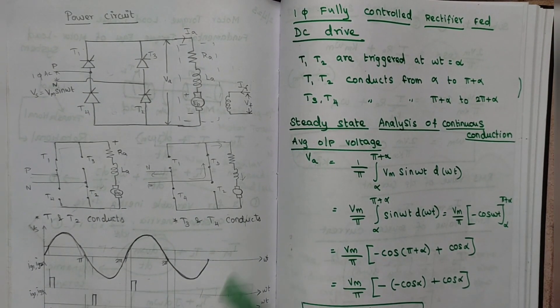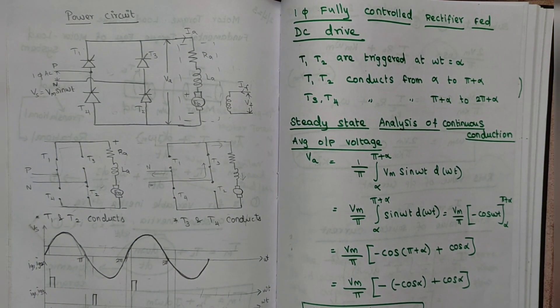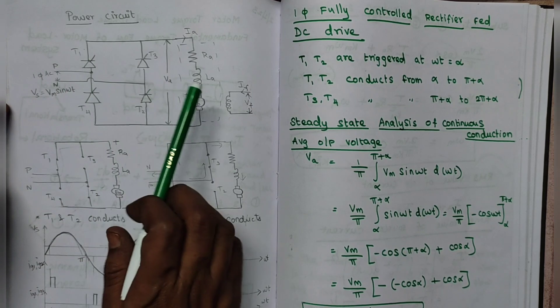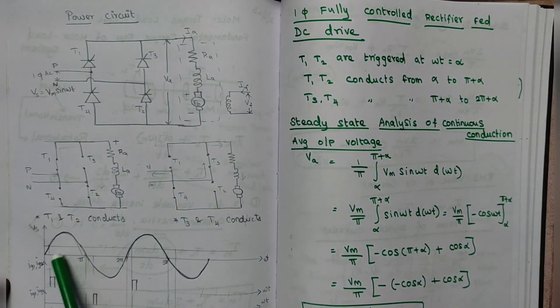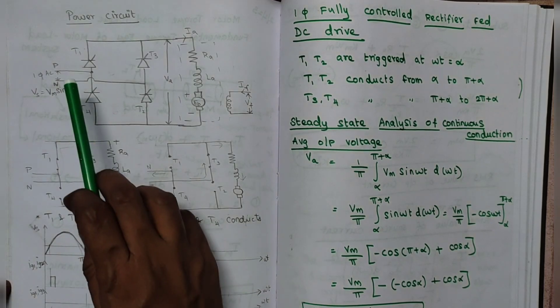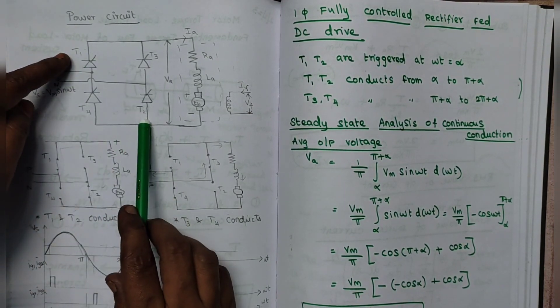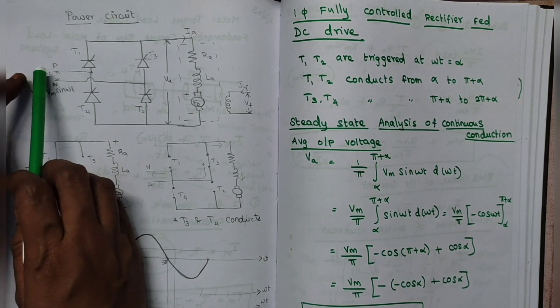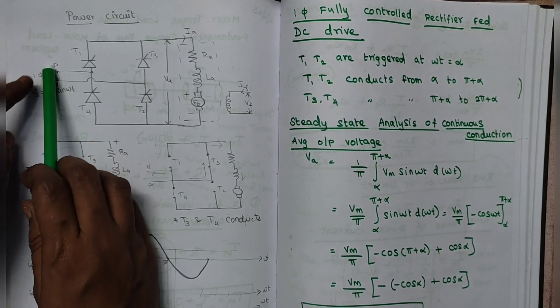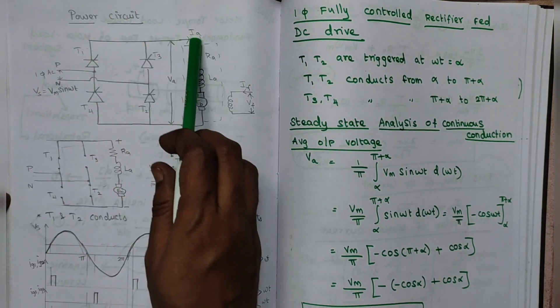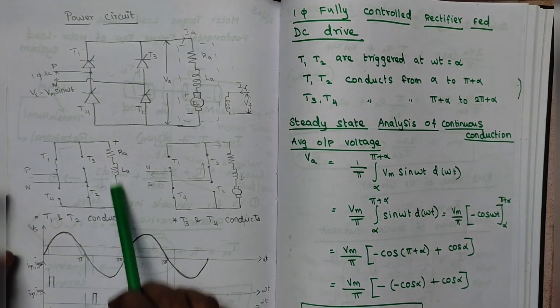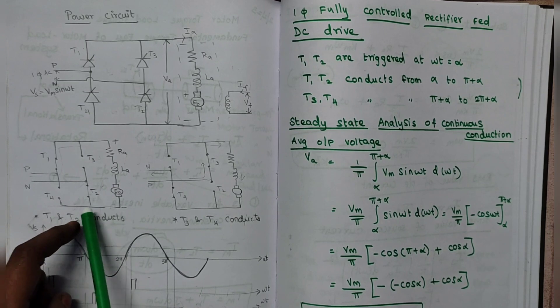Let us see that in the waveform too. If the armature current is not continuous then we call it discontinuous conduction. The input is AC and the output is DC. For the positive half cycle thyristors T1 and T2 conduct, and for the negative half cycle T3 and T4 conduct. For the positive half cycle, current flows via thyristor T1, through the motor, then to T2 and back to negative.